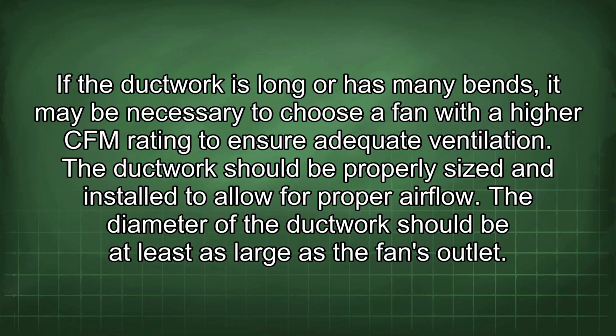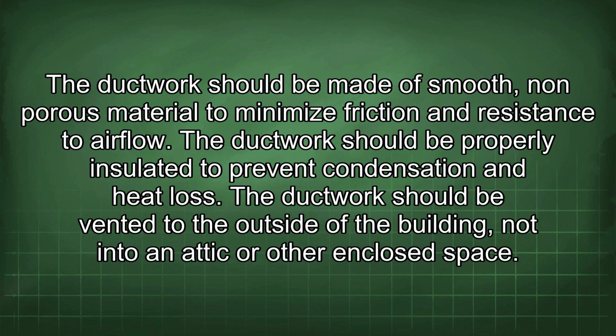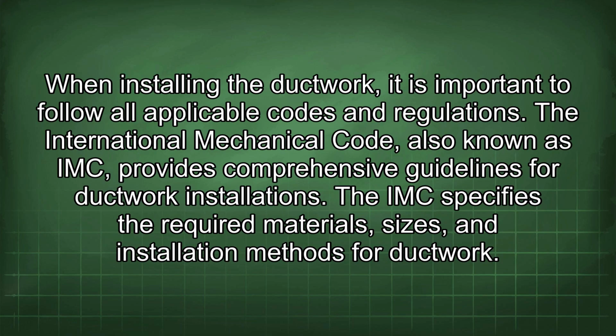The ductwork should be properly sized and installed to allow for proper airflow. The diameter of the ductwork should be at least as large as the fan's outlet. The ductwork should be made of smooth, non-porous material to minimize friction and resistance to airflow. The ductwork should be properly insulated to prevent condensation and heat loss. The ductwork should be vented to the outside of the building, not into an attic or other enclosed space. When installing the ductwork, it is important to follow all applicable codes and regulations. The International Mechanical Code, also known as IMC, provides comprehensive guidelines for ductwork installations.